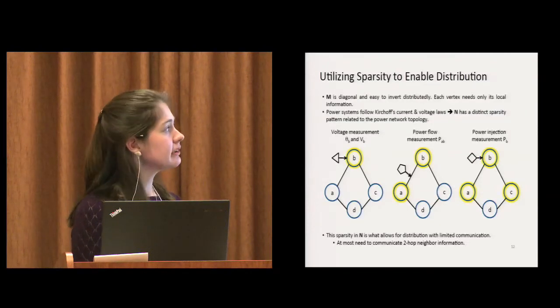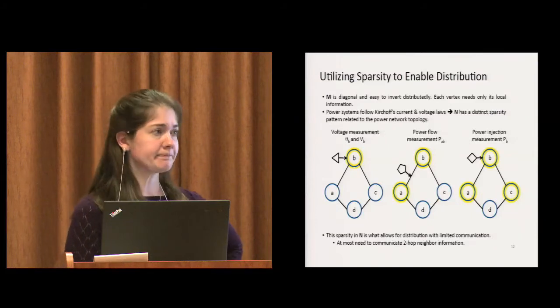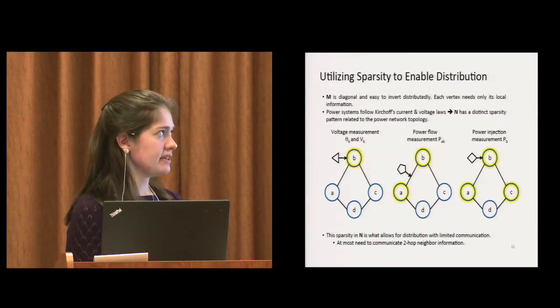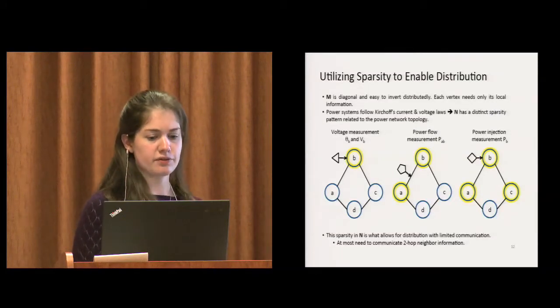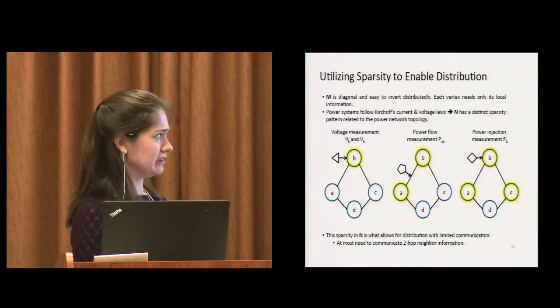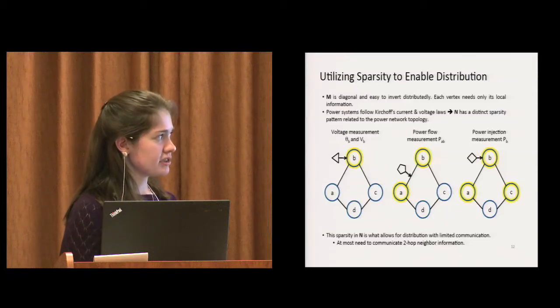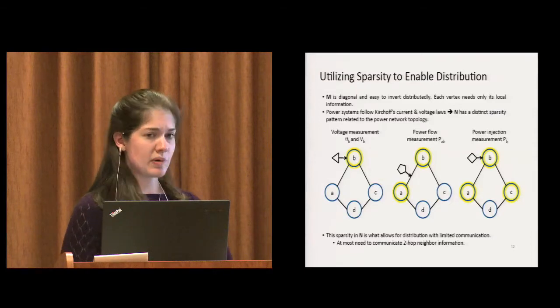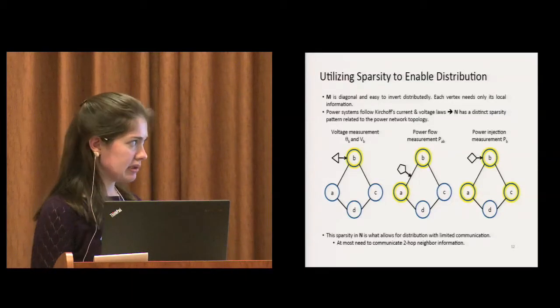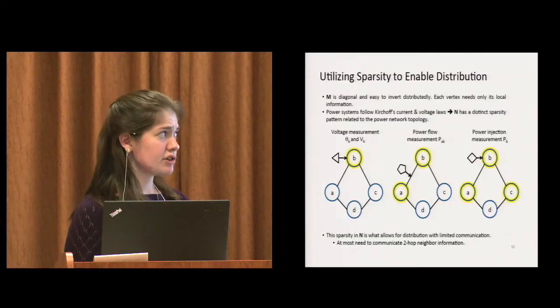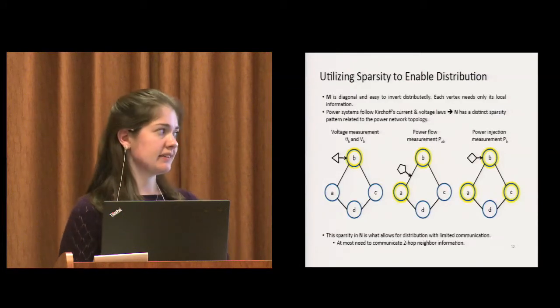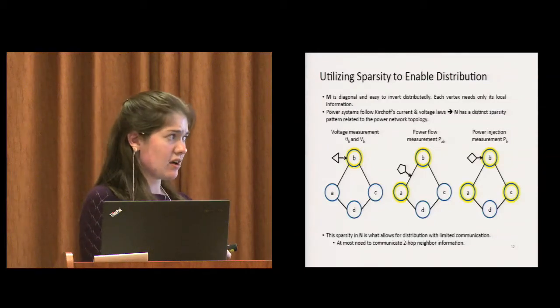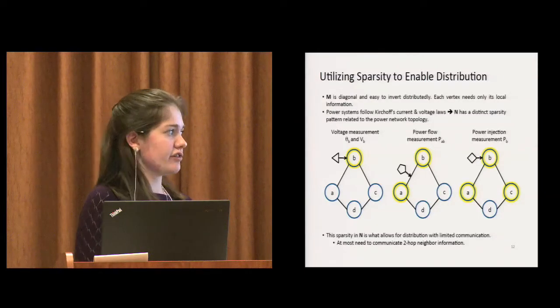Here are the three different measurements that we look at. If we measure the voltage directly at B, that measurement only depends on the voltage at B, which is kind of trivial. But for power flow measurements, if you measure the power flow between A and B, that measurement only depends on the voltage at A and B. Lastly, if you measure power injection at B, that measurement depends only on the voltage at B and B's neighbors, A and C, and not anything further out in the network.